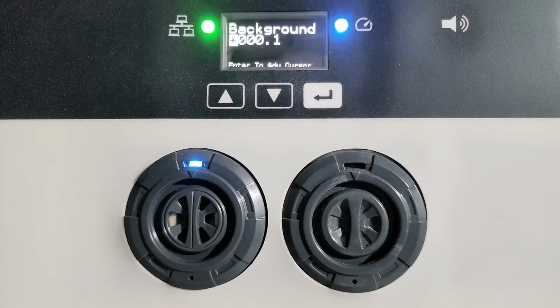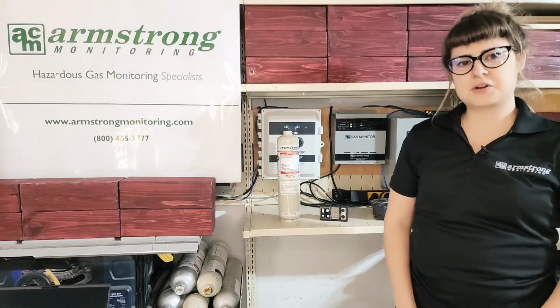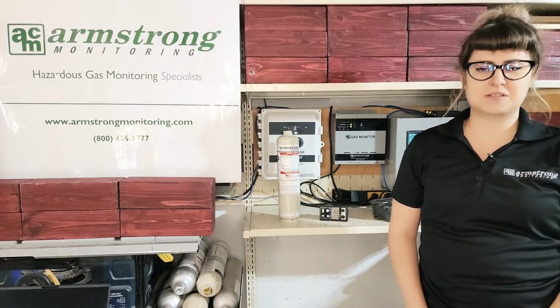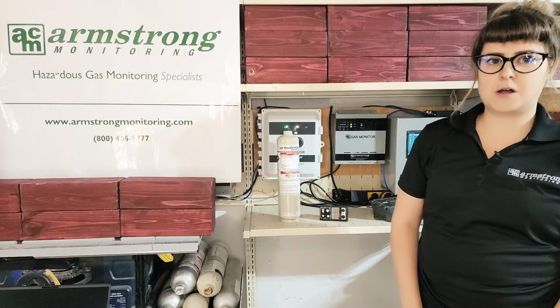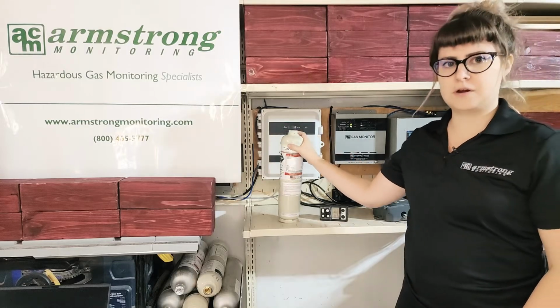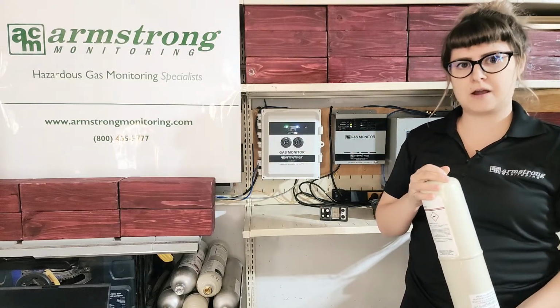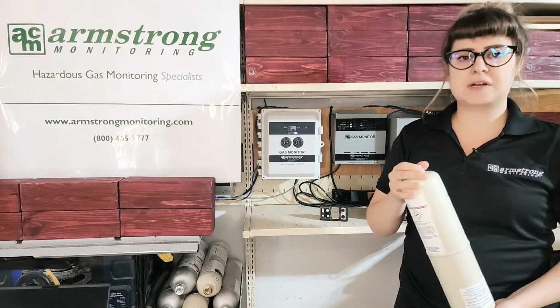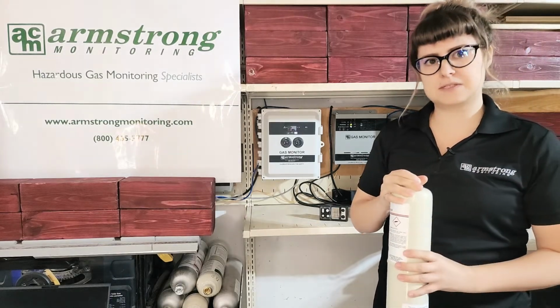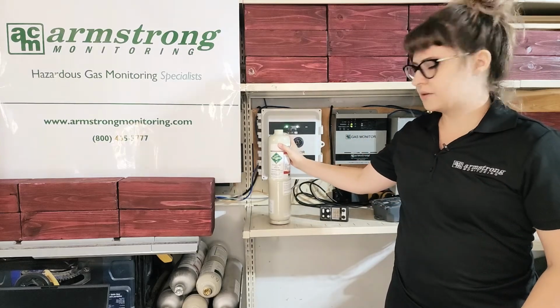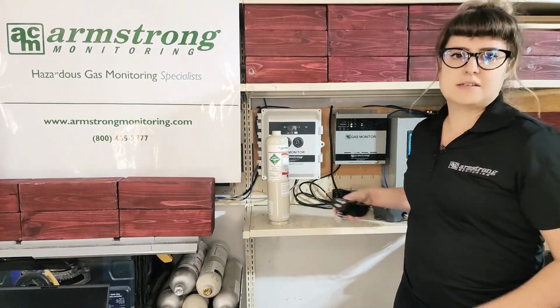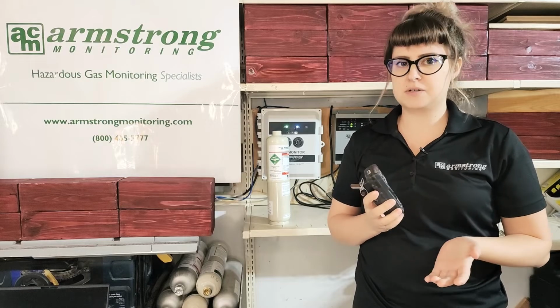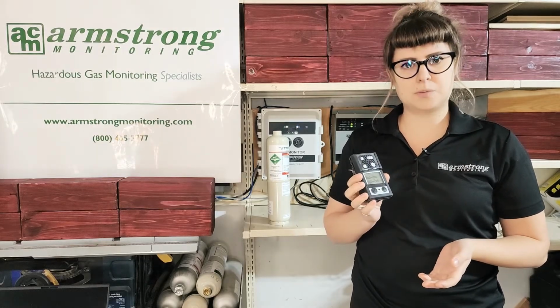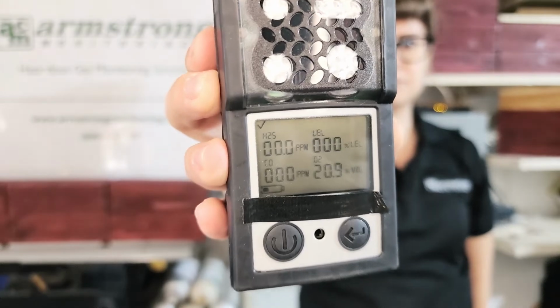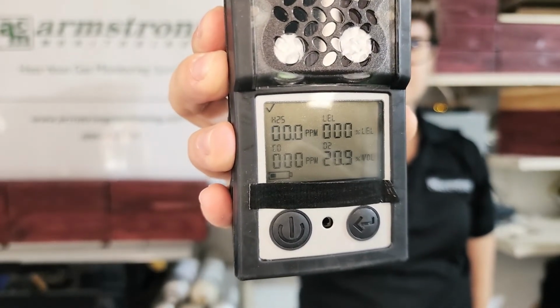You'll next be prompted to enter a background concentration. There are different ways to set the background during zero calibration. One of the more common methods is to use a pure nitrogen or zero air calibration cylinder to apply to the device during the finding zero step. Another option, if you have access to a trusted secondary gas monitor, such as a handheld or portable, you can use this to verify the background concentration of your ambient environment.